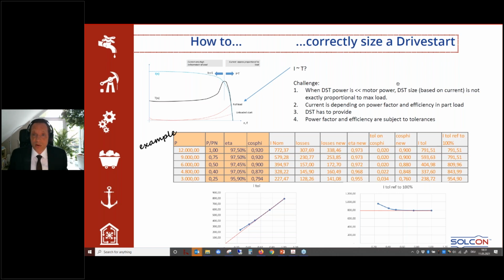What you need to do to correctly size a drive start or a VFD starter is, I said the current is approximately proportional to the torque, but when the starting power is much lower than the motor power, the drive start size is not exactly proportional. What does this mean? Here you have an example of a motor. Let's say in this case it was 12 megawatt, and you see here that the efficiency and power factor are getting worse with smaller rating. So that means the current is no longer on the theoretical curve, the red curve, but here in this case is getting higher.